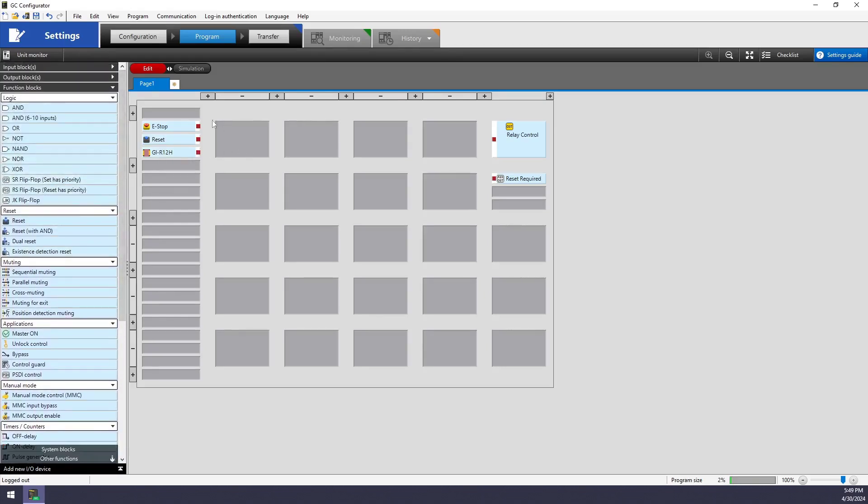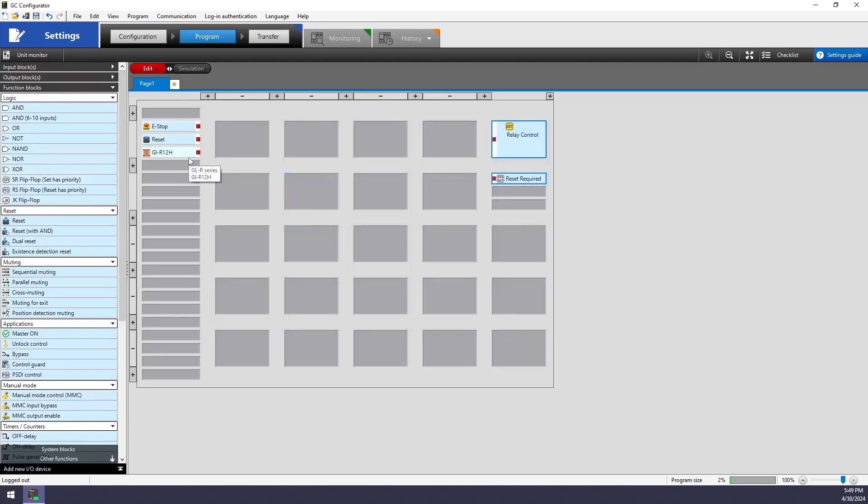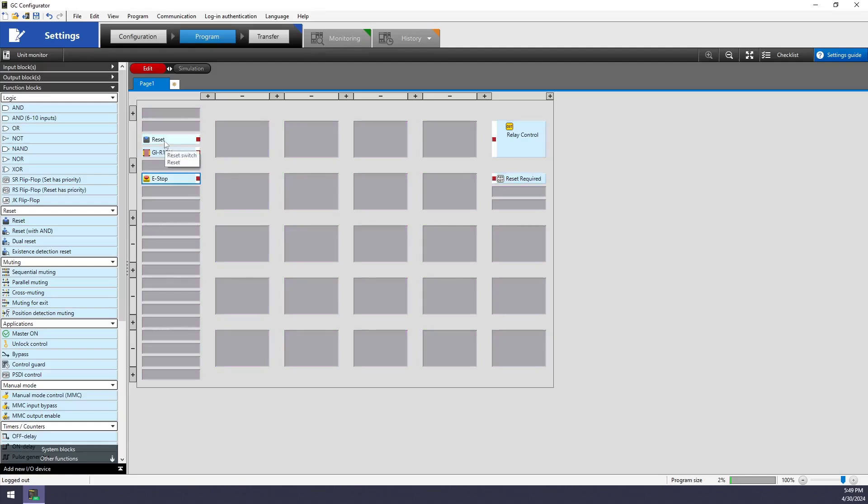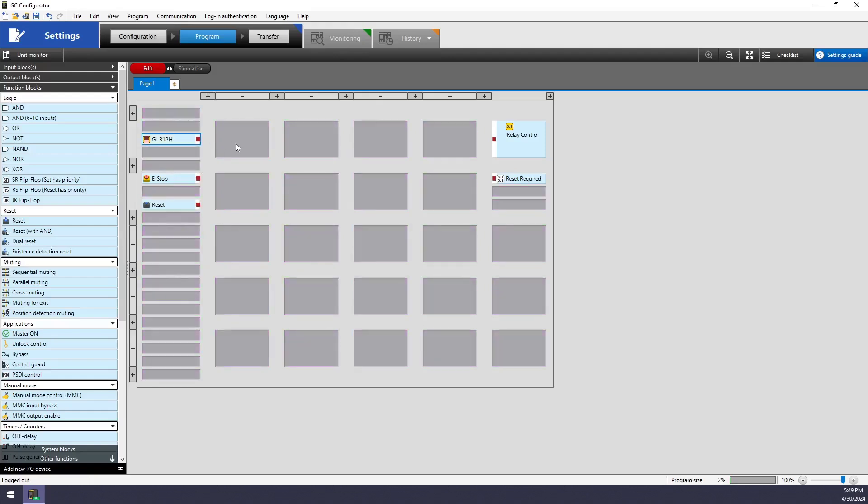Whenever I get into the actual programming here, so in the middle of the screen, I typically start by saying, okay, which devices are going to be an automatic reset and which devices are going to be a manual reset. So for manual reset, I'm actually going to want this e-stop and its reset push button to provide the manual reset function.